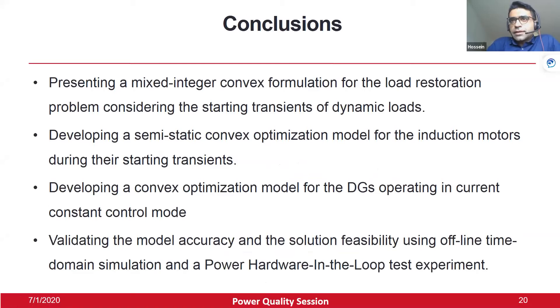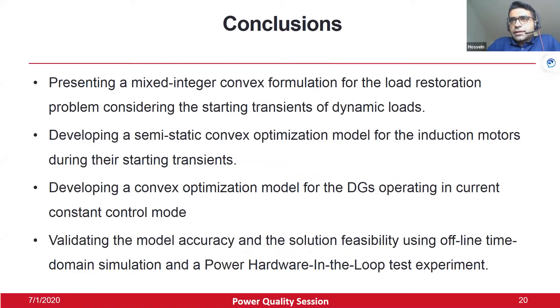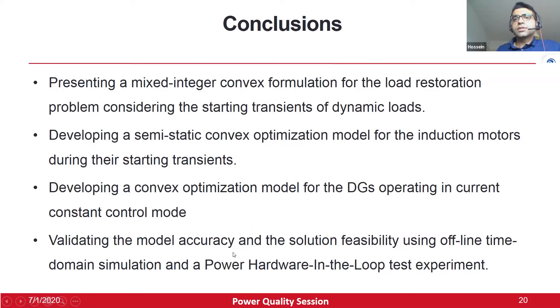In conclusion, we presented a mixed-integer convex formulation for the load restoration problem considering the starting transients of dynamic loads, namely induction motors. We developed a semi-static convex optimization model for the induction motor and a convex optimization model for DGs operating in current constant mode. The accuracy of the derived model was validated using both offline time-domain simulation and a power hardware-in-the-loop test experiment. Thank you very much for your attention.